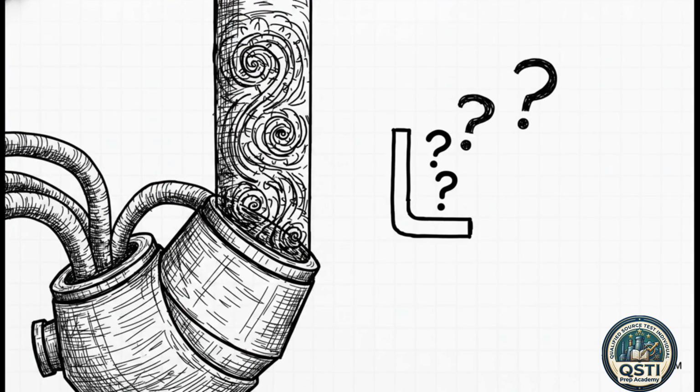So, why does cyclonic flow even happen? Because industrial equipment is super aggressive. If your site is downstream of a cyclone, an inertial demister, a venturi scrubber, or a stack with a tangential inlet, that exhaust air is going to be spinning. And when the air spins, it's no longer flowing parallel to the stack walls. That means our standard pitot tubes simply can't measure the velocity accurately.